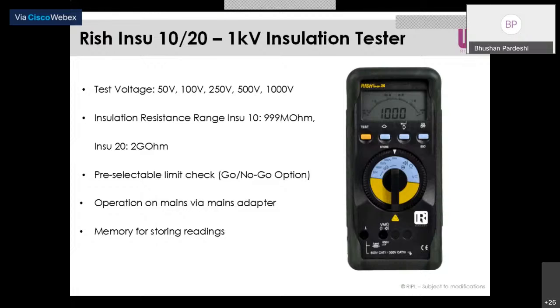So basically 1 kV comes with two variants. You can see Rishabh RISH Insu 10 and RISH Insu 20. So RISH Insu 10 comes with 1 gigaohm measurement, and RISH Insu 20 comes with 2 gigaohm measurement. In both models, test voltage is given in steps of 50 volt, 100 volt, 250 volt, 500 volt, and 1000 volts. It also has a pre-selectable limit check, that is the go/no-go function, which we have already explained in the previous slides on the multimeter.